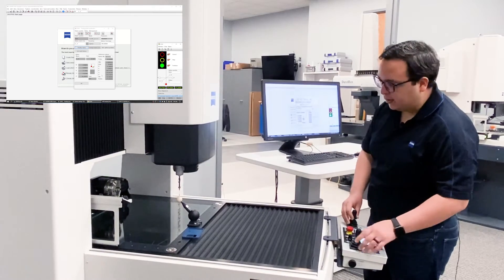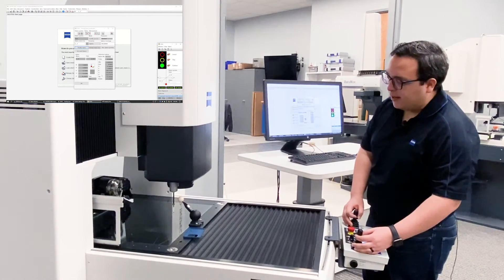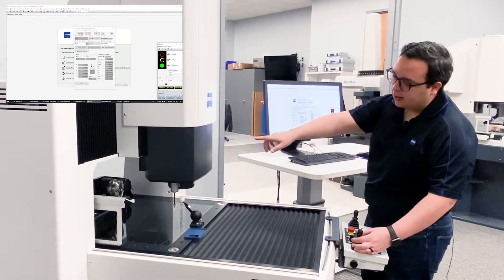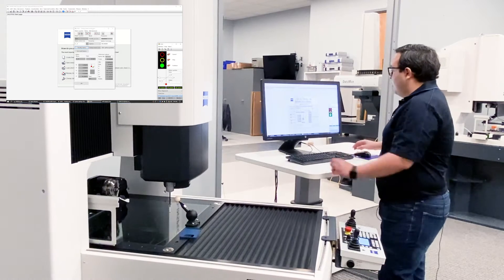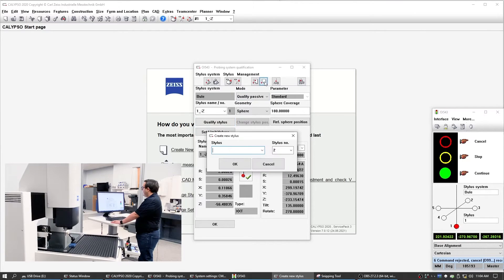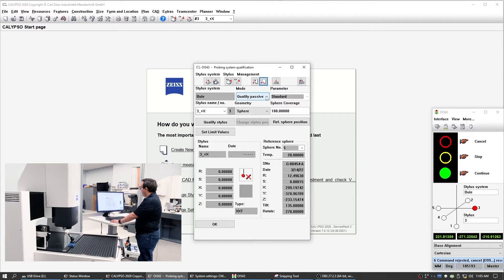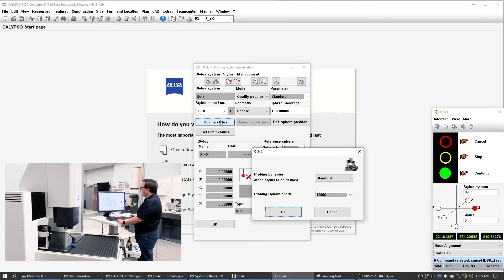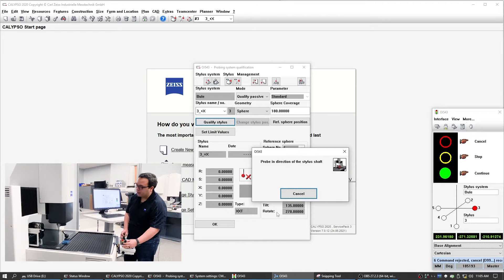Now we're going to go to this other stylus system, and I'm going to keep the nomenclature that we normally teach in our Calypso basic class. In Calypso basic, we always do: the one going in the down direction is 1_minus_Z, the one going in the plus Y direction is 2_plus_Y, and then in the X is 3_plus_X. So we're going to do stylus number three — 3_underscore_plus_X direction. We're qualifying passive, making sure that it's on the correct reference sphere, and let's go ahead and qualify this. We're doing it standard because we're measuring a metal part.